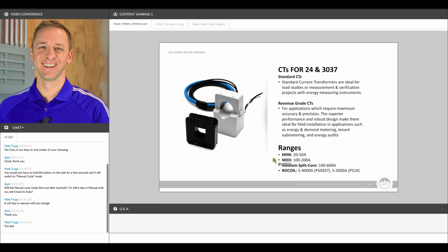These CTs are also available in revenue grade versions. The CTs have to be ordered specifically for revenue grade applications, and so they can be used in any tenant billing or high accuracy demand applications. The ranges for the mini and MIDI go from up to 20 to 50 amps. There's the MIDI size, and this is going to go up to either 100 or 200 amps. There's the medium style split core, and these can go up to anywhere from 100 to 600 amps. And then we have the Rogowski coil rope CTs that can go up to 4,000 to 5,000 amps, depending on which meter they're communicating to.